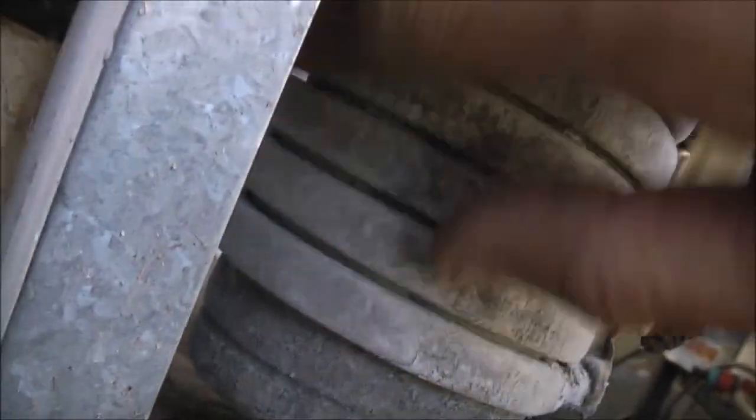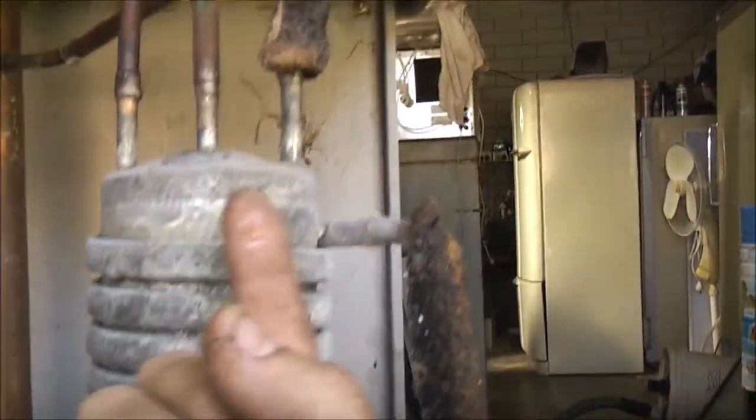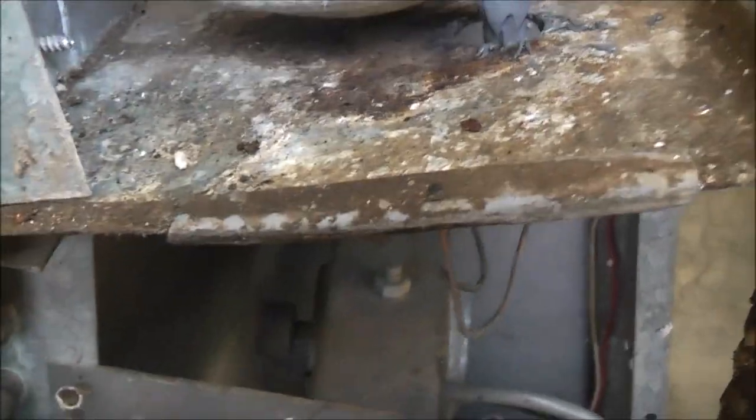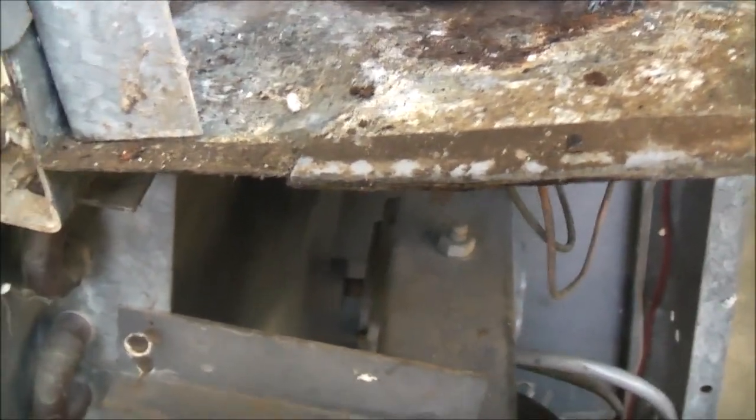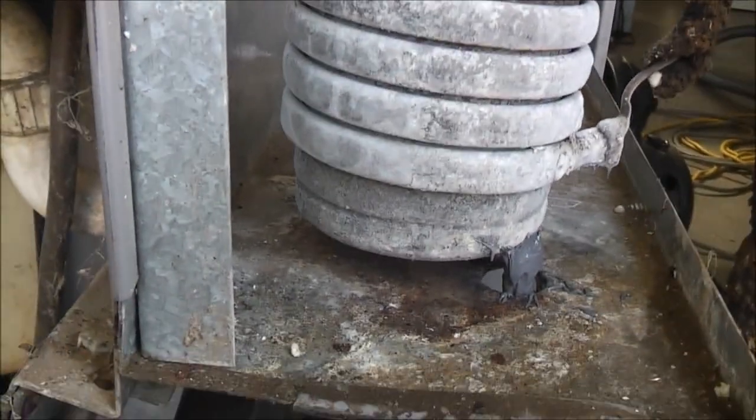I've put a new thermostat on it. The thermostat went inside, right up through, and ended about here. The old thermostat was completely buggered. I took it out. Actually, this tube filled all with water, all the way into the bellows. That's not supposed to happen. I had to drill it out, pull the old sensing tube out, and stuck in a new thermostat.